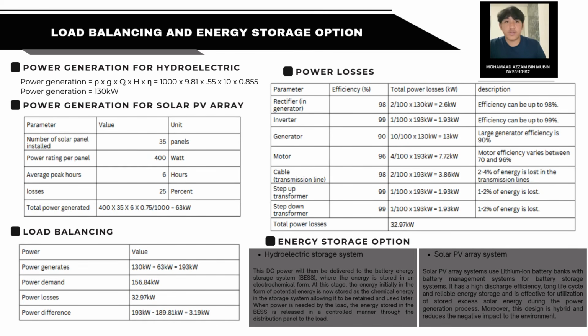Lastly, for the energy storage option, we use a battery energy storage system for the hydroelectric to manage the flow. The hydroelectric AC power is rectified to DC power, while the solar PV array system is regulated via a DC-DC converter to prevent overcharging. This energy is stored in electrochemical form using lithium-ion battery banks, which allow us to capture the excess solar energy during the day and release it at night, ensuring that the facility and the village never face a power shortage. That's all from me.